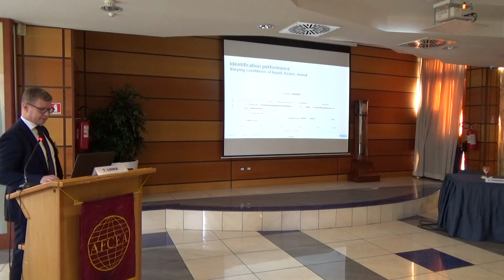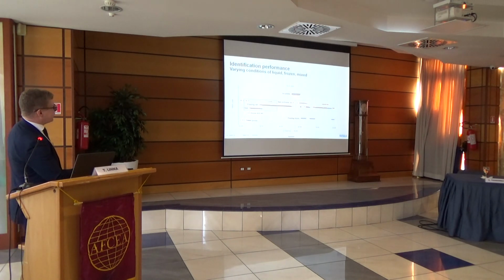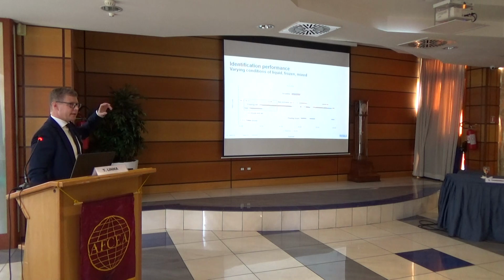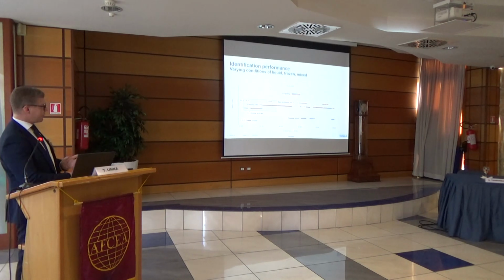What is very interesting in the next step is that there are ice pellets, which is of course an indication that there is a freezing layer aloft, higher in the atmosphere. Both the observer and FD70 agree there. And then even more interestingly, in the next step, FD70 keeps on reporting freezing rain, and then rain and snow, while the observer degrades down to freezing drizzle.